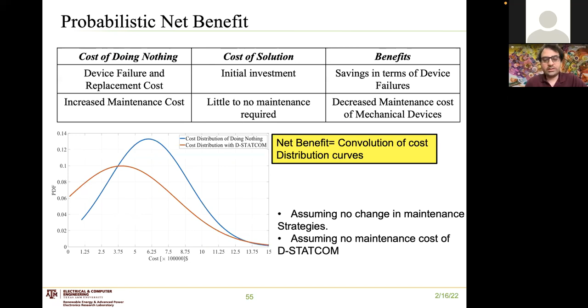But when we have D-STATCOM on our network and we redo the failure analysis, the expected value of the cost curve is roughly closer to $400,000. So that's a saving of $200,000 over a lifespan of 30 years, assuming we don't change our maintenance strategies and assuming there's no maintenance cost involved in D-STATCOM.